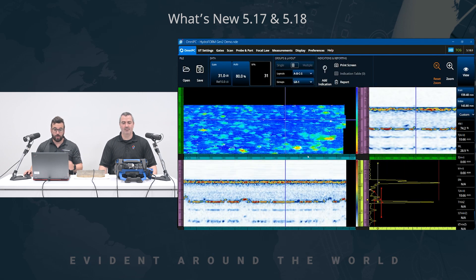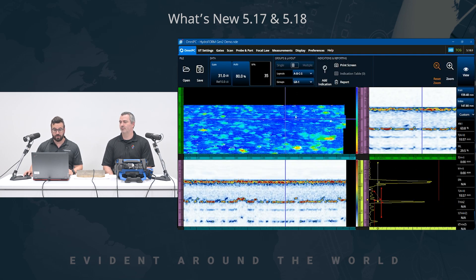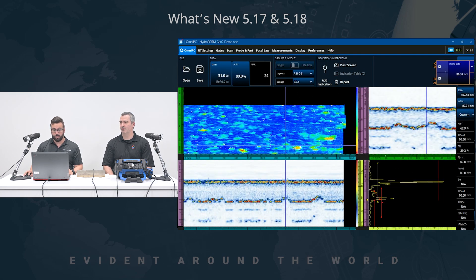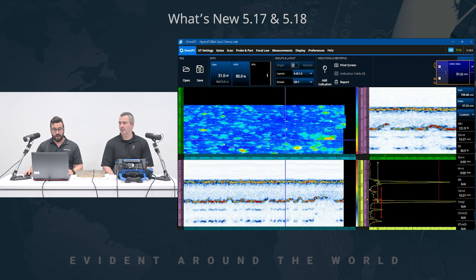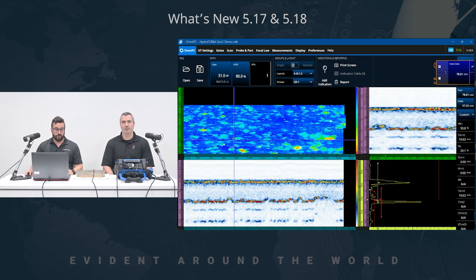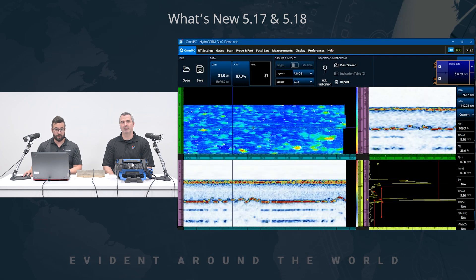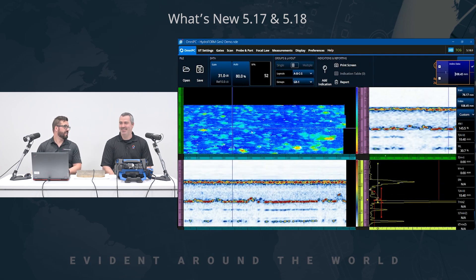So if I'm going back to this corrosion map we have here, we can see we just increased the performance in index scan. If I move it like this very quickly, you can see there is no more lag anymore. And also, we increased the performance on this side too. That will be easier for the inspector to do the analysis on that part. So as you move both index and scan data cursors, the linked views refresh live. More performance and a better feel for the user at the end of the day.